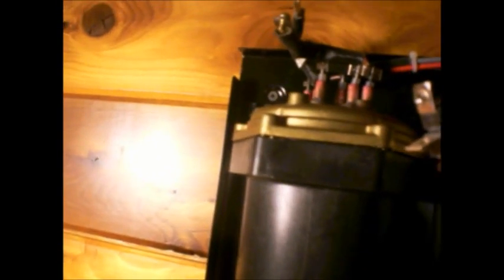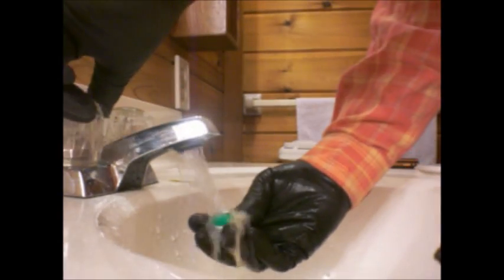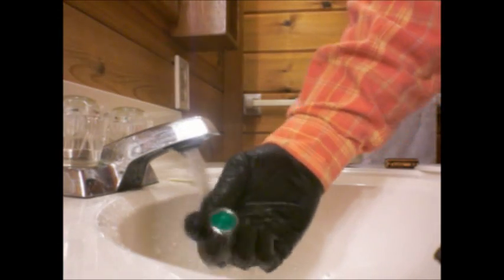Problem found. Found out why the element's shorting. The entire pot is full of hard water sediments and it ain't coming out. Cranking on it, it's jammed in there. I'm thinking if I screw around with this I'm going to regret it. They'll have no hot water. At least now they have hot water until the over limit trips. Time to put it back together. I could remove this pot, undo the fittings, take the screws off, but it could be cooked into this hard plastic. I'm going to put it back together and go buy a brand new hot water tank. I just cleaned this twice. Sediment, hard water. Nothing's ever simple, like my transmission in my Suburban.